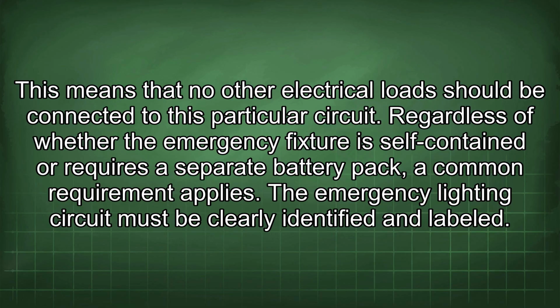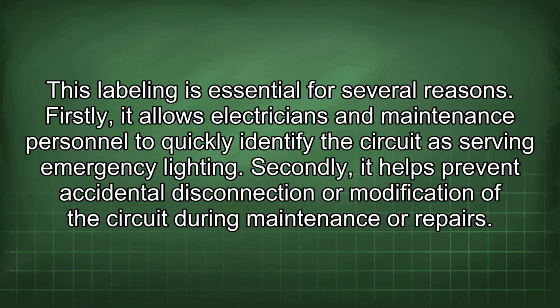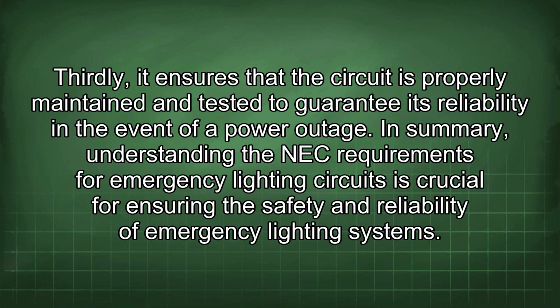Regardless of whether the emergency fixture is self-contained or requires a separate battery pack, a common requirement applies. The emergency lighting circuit must be clearly identified and labeled. This labeling is essential for several reasons. Firstly, it allows electricians and maintenance personnel to quickly identify the circuit as serving emergency lighting. Secondly, it helps prevent accidental disconnection or modification of the circuit during maintenance or repairs.